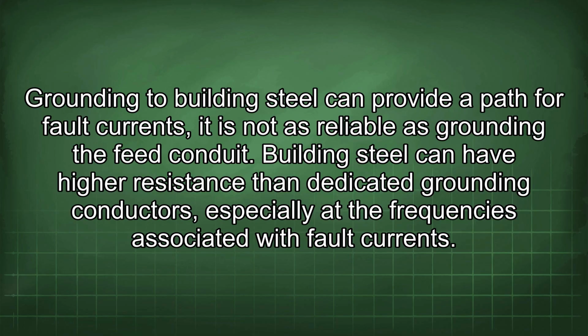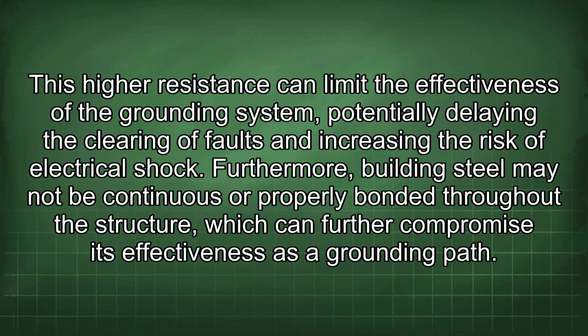Grounding to building steel can provide a path for fault currents. It is not as reliable as grounding the feed conduit. Building steel can have higher resistance than dedicated grounding conductors, especially at the frequencies associated with fault current. This higher resistance can limit the effectiveness of the grounding system, potentially delaying the clearing of faults and increasing the risk of electrical shock.